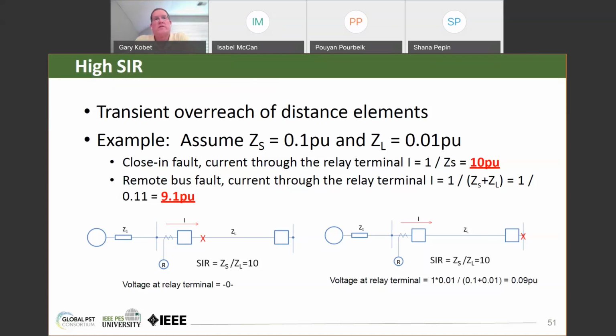Pilot relaying on lines that have a high source impedance ratio is one solution for that. Line current differential is one form of pilot relaying that may work for that. There is a working group in the Power System Relay Committee, D38, that is working on this issue. And I have a few more slides here.